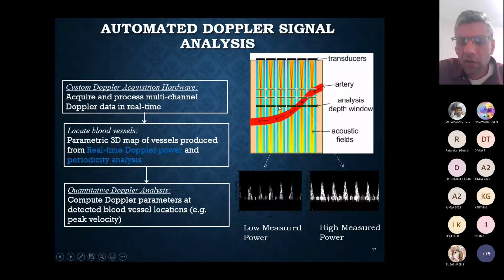So here you see the illustration of a blood vessel. The acoustic beams are shown here. And essentially, as you can imagine, wherever the acoustic beam intersects the blood vessel, you're going to get a very strong Doppler signal, right? So essentially, for every pixel here, you can actually create a blood flow profile, which is shown on the bottom. Wherever the blood flow intersects the beam, you will have a higher power, so higher intensity. Wherever the blood flow is not present or it's very weakly present, you will have a low intensity.